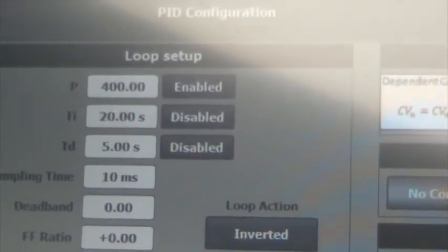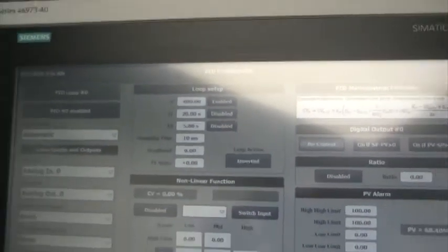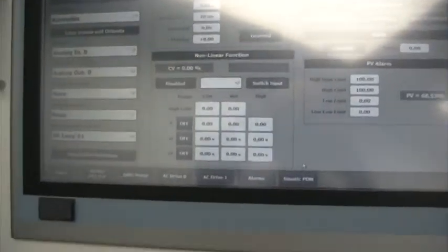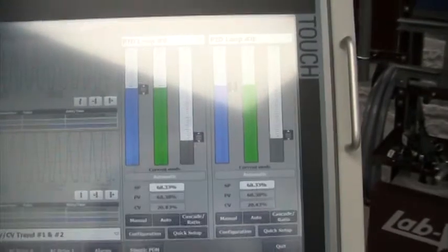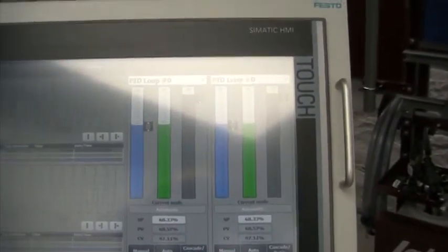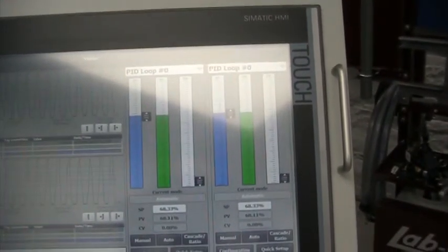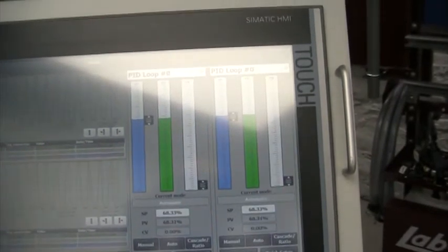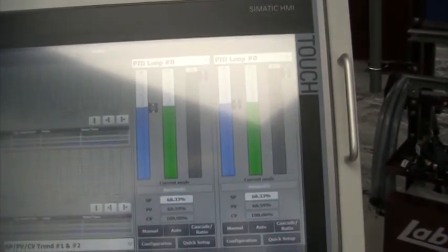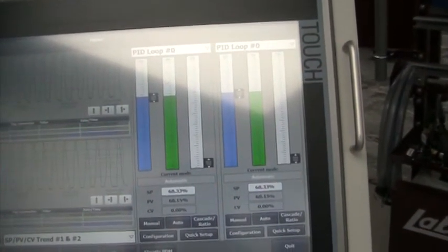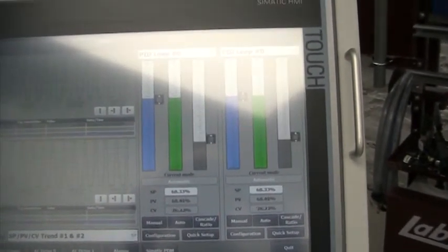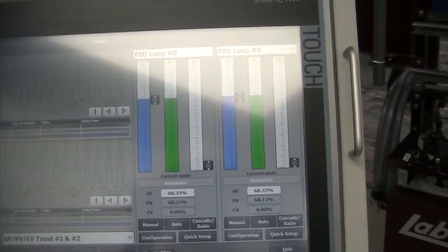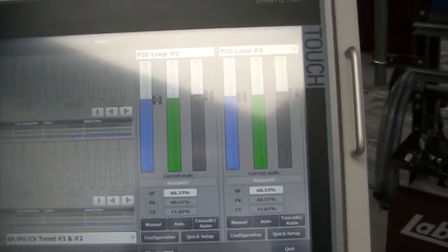That's a very large value. And that's why you hear the pneumatic controller work very hard. The pressure is changing a lot from 0 all the way to 100. The pressure is not changing from 0, it's from 3 psi to 15 psi. That's the range that will open and close the pneumatic control valve.